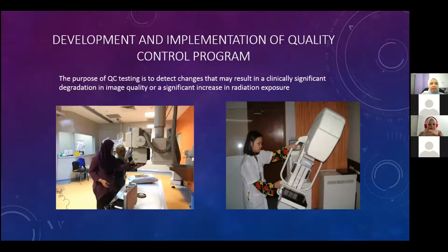The QC tests include generator performance like kV accuracy and output exposure consistency, image quality, X-ray beam alignment, and dosimetry. Medical physicists are not only able to perform the QC test, but also must understand the operation of the imaging equipment and factors that affect the radiographic output. The purpose of QC testing is to detect any changes that may result in a clinically significant degradation in image quality or significant increase in radiation exposure.